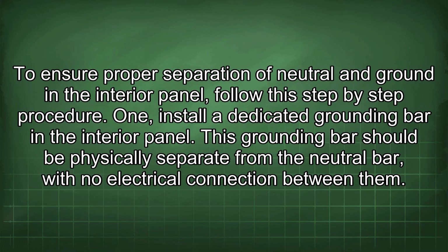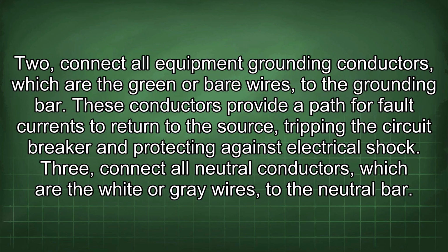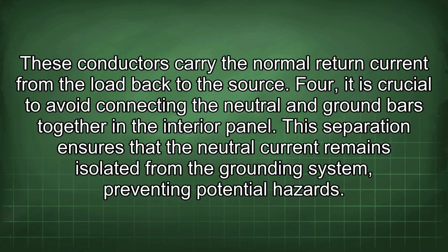1. Install a dedicated grounding bar in the interior panel. This grounding bar should be physically separate from the neutral bar, with no electrical connection between them. 2. Connect all equipment grounding conductors, which are the green or bare wires, to the grounding bar. These conductors provide a path for fault currents to return to the source, tripping the circuit breaker and protecting against electrical shock. 3. Connect all neutral conductors, which are the white or grey wires, to the neutral bar. These conductors carry the normal return current from the load back to the source. 4. It is crucial to avoid connecting the neutral and ground bars together in the interior panel. This separation ensures that the neutral current remains isolated from the grounding system, preventing potential hazards.